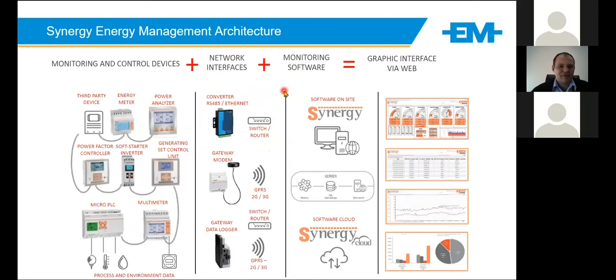Quite a busy picture we have here, but to give you a big brief view, we've got monitoring and control of devices. So I could have a third-party device, an energy meter, an analyzer, a soft starter, gensets, multimeters, PLCs, giving me data. In this case, it's typically Modbus, RS-485. I would need to take that Modbus signal, that RS-485. I may need to convert it onto an Ethernet connection or a GSM connection or via logger. And then I get presented to the Synergy pack.